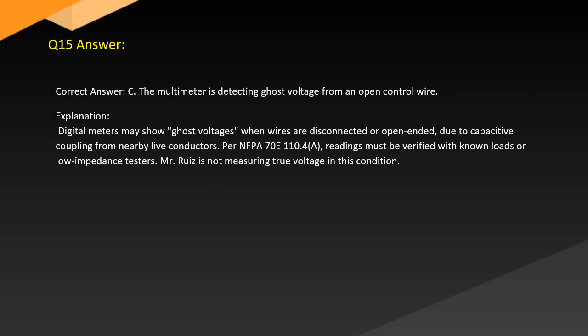Answer. Correct answer: C. The multimeter is detecting ghost voltage from an open control wire. Explanation. Digital meters may show ghost voltages when wires are disconnected or open-ended due to capacitive coupling from nearby live conductors. Per NFPA 70E 110.4(A), readings must be verified with known loads or low impedance testers. The technician is not measuring true voltage in this condition.